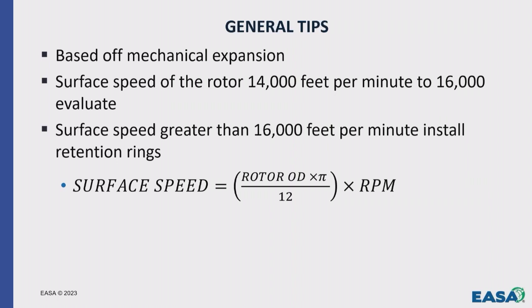Now you can go through and do all sorts of finite element analysis, or you can pay engineers to do a lot of in-depth studies to see exactly what is needed. But what we've found is that by using a simple set of rules, you can determine if a rotor has to have a stainless steel ring or not. So under 14,000 feet per minute, and the equation's right there, I never worry about it because copper in itself, its mechanical properties will easily handle that kind of force. So they're not going to expand, they're not going to grow, they're not going to break.